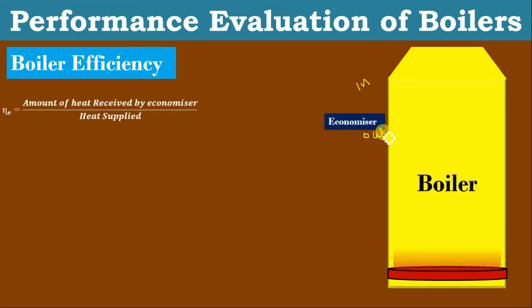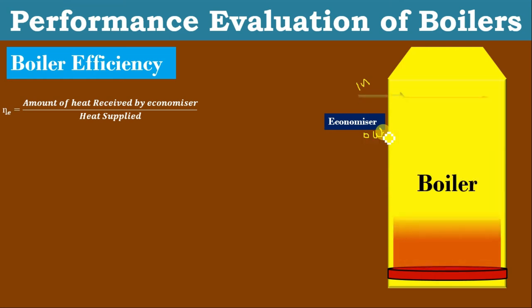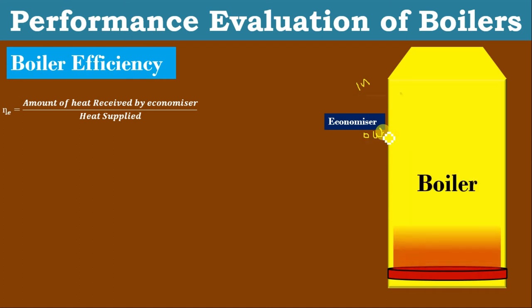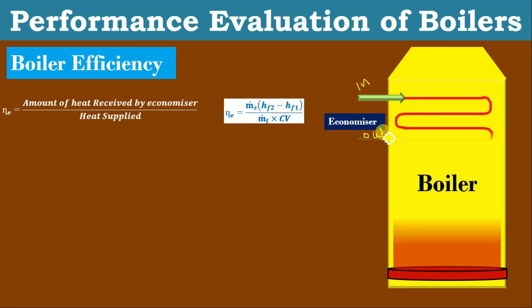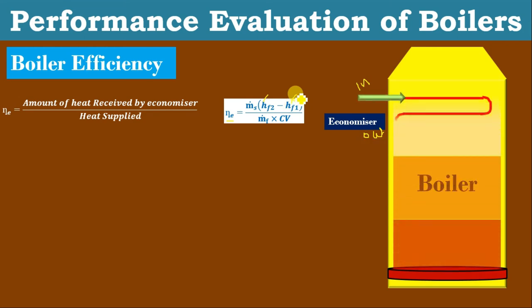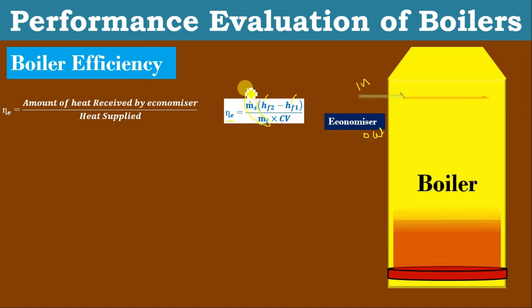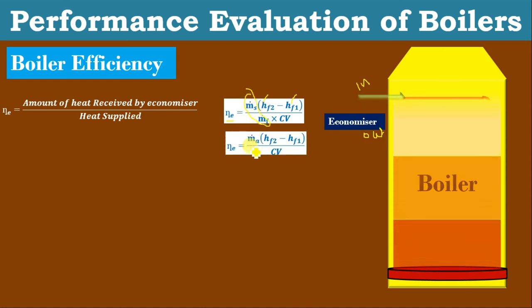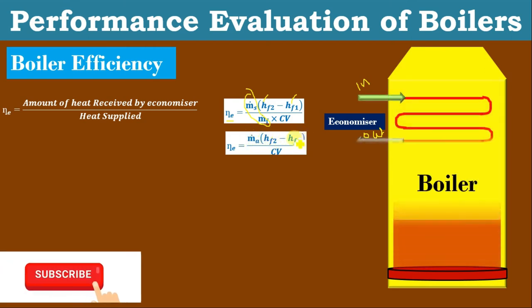To find out the efficiency of the economizer, that is the amount of heat received by the economizer: the mass of water supplied multiplied by the enthalpy difference gives the amount of heat received by the economizer, divided by heat supplied, that is Mf × Cv. So, efficiency of the economizer = mass of steam generated × (outlet economizer enthalpy − inlet economizer enthalpy) / (Mf × Cv). This equation can be written as: efficiency of economizer = actual evaporation ratio × (outlet enthalpy of economizer − inlet enthalpy of economizer) / Cv.